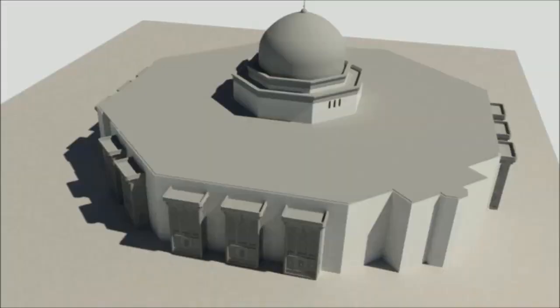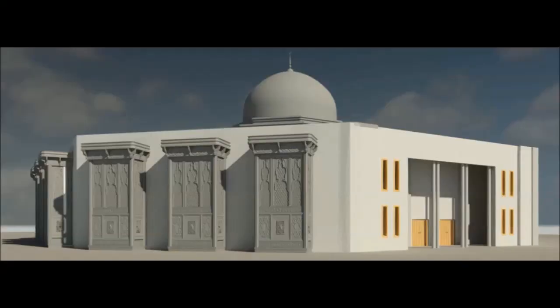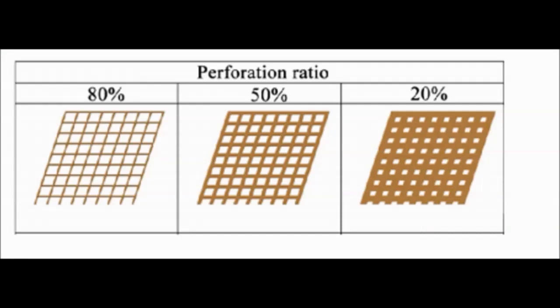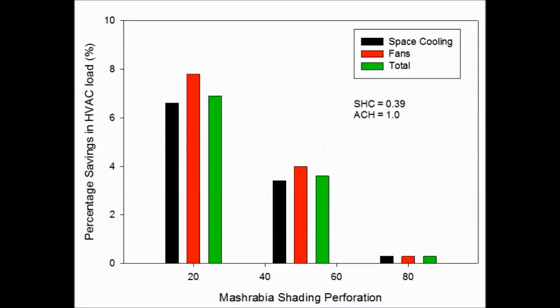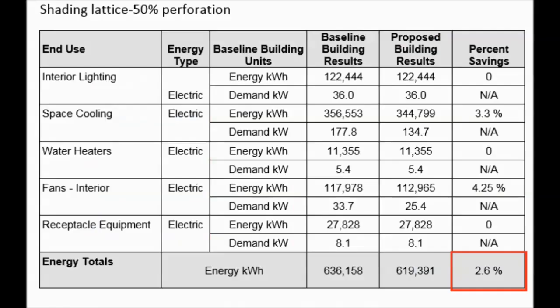The effect of introducing Arabic lattice shading to the building windows has been studied prior to deciding which value of perforation ratio should be considered. The figure shows a good impact of almost 4% energy savings in cooling load for a perforation ratio of 50%. This work adopted a lattice with a perforation ratio of 50%. This will lower the total energy consumption of the building by almost 2.6%.